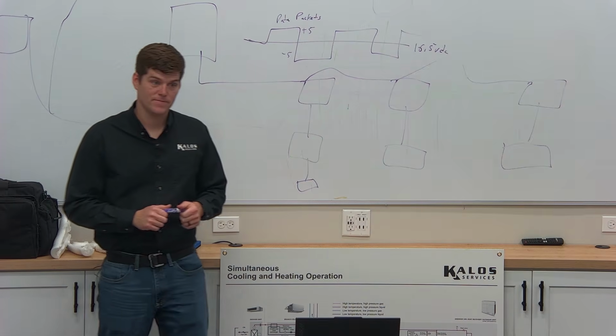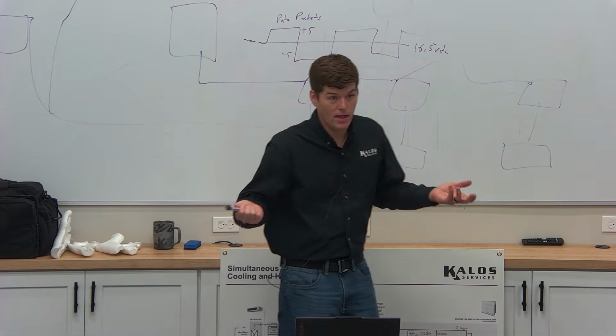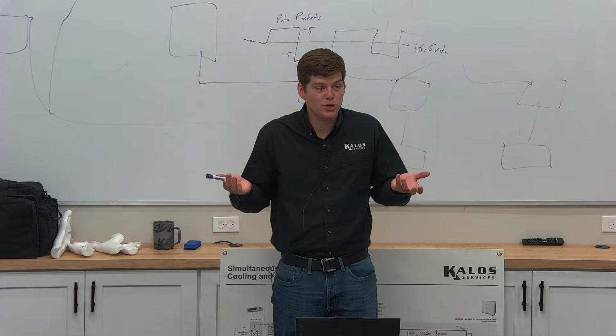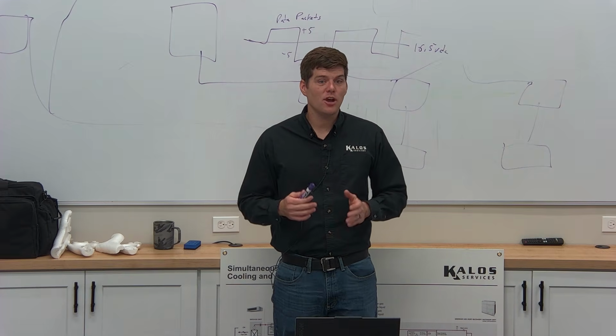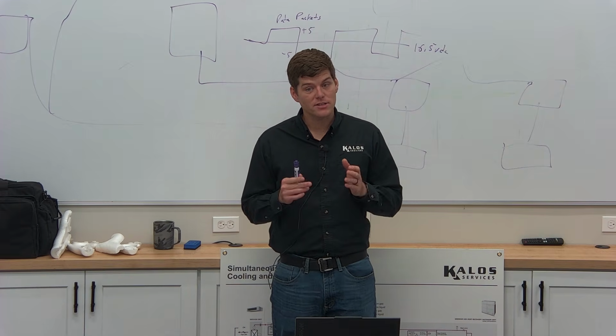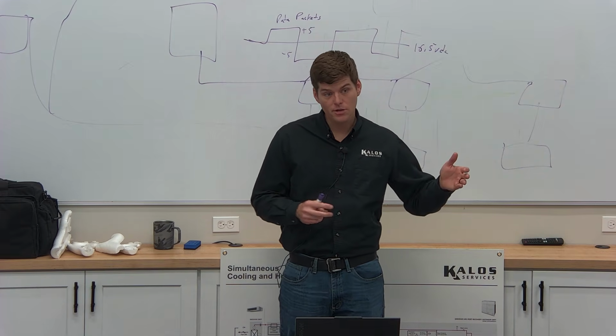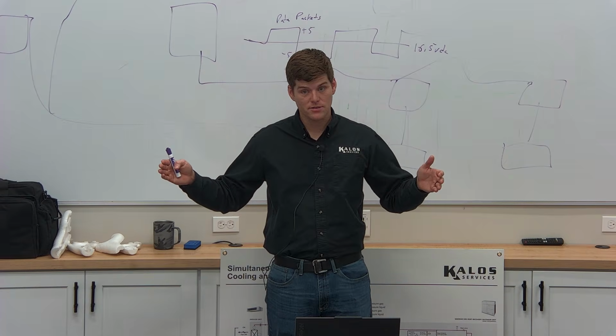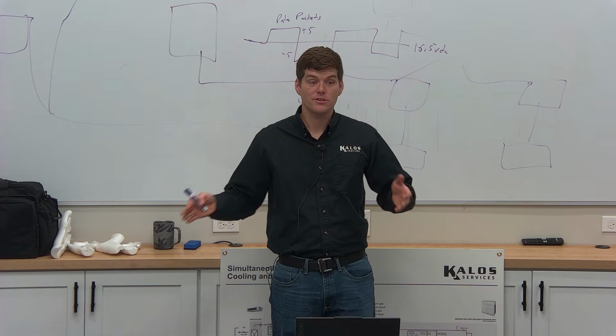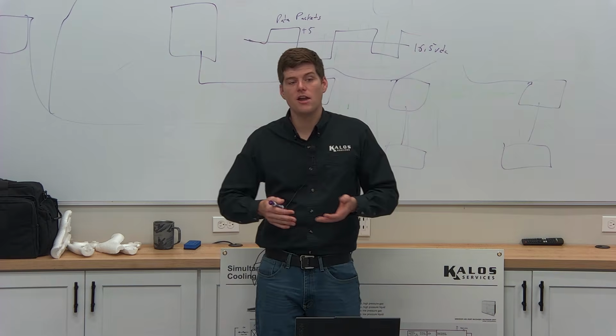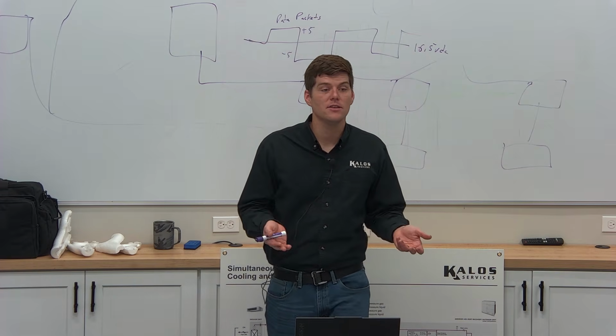Working around. To know if it's cooling properly. How else will we know? We just assume? These have electronic expansion valves that are designed to adjust from 0 to 2,000 pulses, microsteps, to deliver a specific amount of capacity. How does it determine how much capacity it needs?